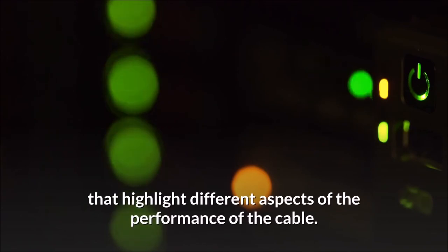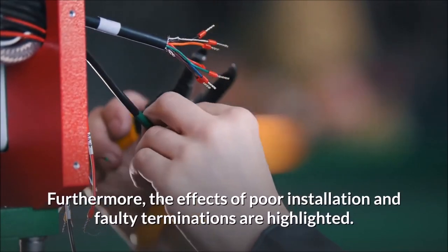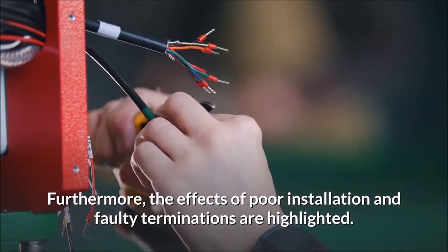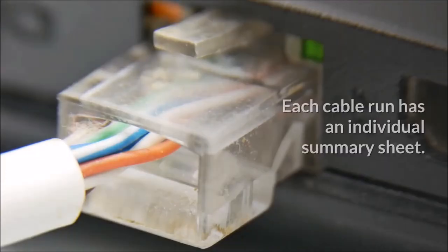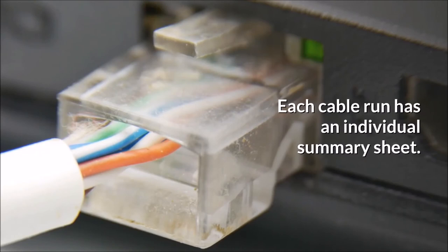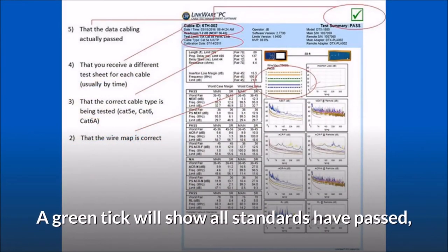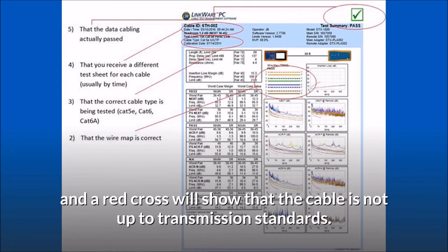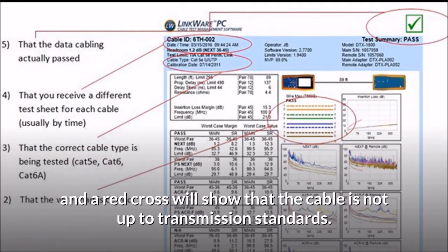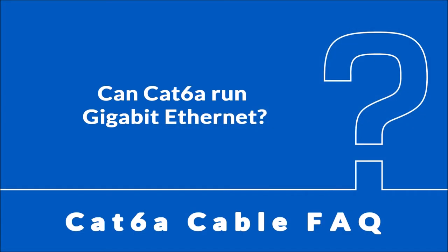This type of tester creates results and charts that highlight different aspects of the performance of the cable. Furthermore, the effects of poor installation and faulty terminations are highlighted. Each cable run has an individual summary sheet. A green tick will show all standards have passed, and a red cross will show that the cable is not up to transmission standards. Can Cat6a run gigabit Ethernet?